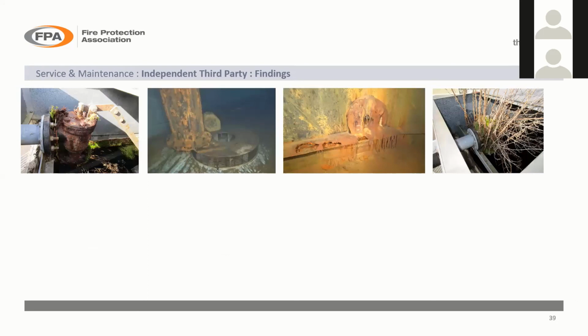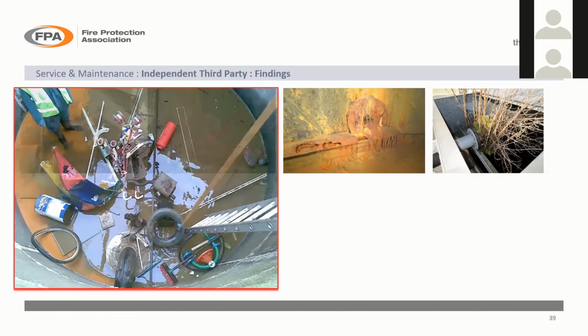And I'm rushing through this, and again, thank you because I have overrun. There are four pictures there of tanks. You can see, obviously, looking inside the tanks, the kind of things that you find. In the first one, the ball valve housing is badly rusted up. And in the right-hand one, something's actually grown out of it. Looks like a garden has grown out of it. But in the middle there, the vortex inhibitors have basically dropped off the pipes, so the pumps may not operate properly, or other things might be sucked into the suction pipes.